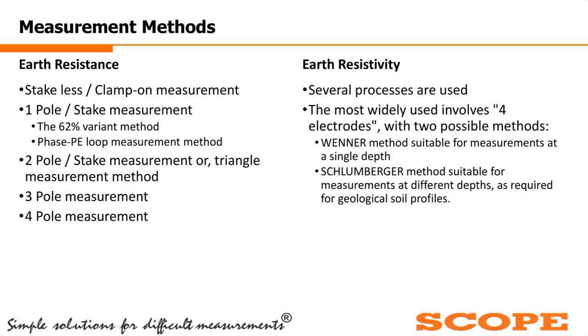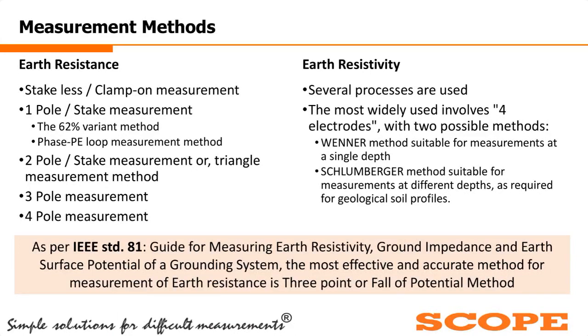Then for the earth resistivity measurement, two methods are widely used, which use 4 electrodes. The first method is the Wenner method, and the other one is the Schlumberger method. These two methods generally vary in the distance between the 4 stakes. Based on this distance between the 4 stakes, different formulas are used for the earth resistivity measurement. As per IEEE standard 81, the fall of potential method or the 3-point earth resistance method is the most effective and accurate method for measuring any type of earth resistivity, ground impedance, or earth surface potential of any grounding system. We will also see all these methods in upcoming slides.